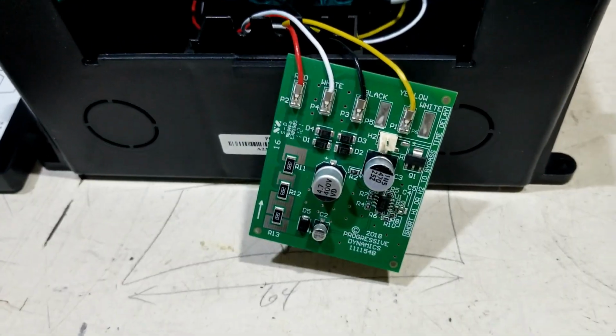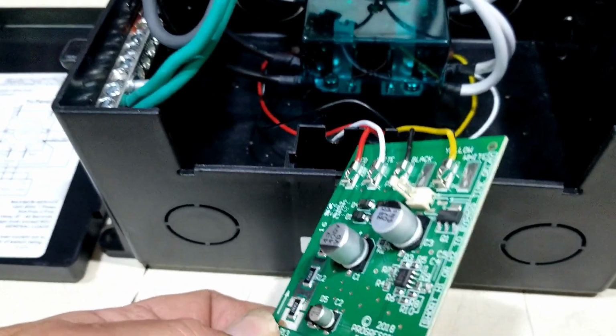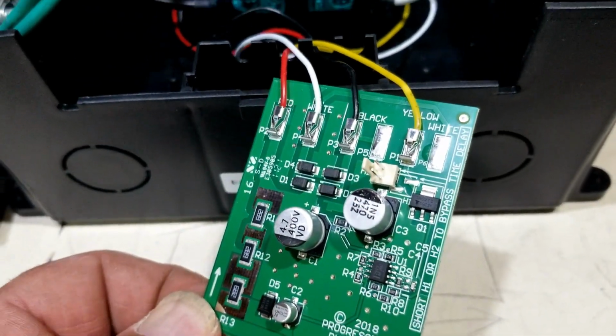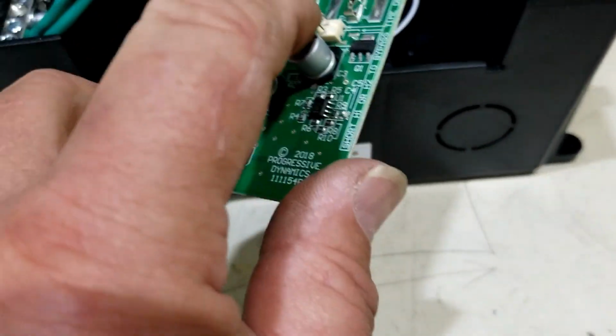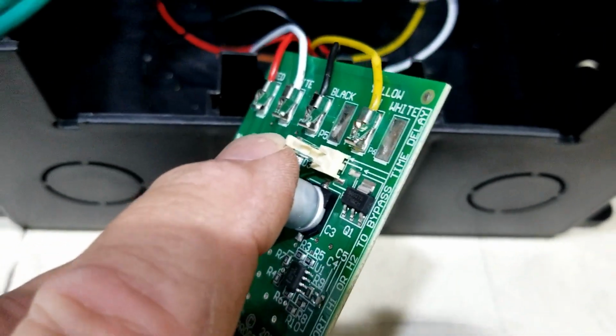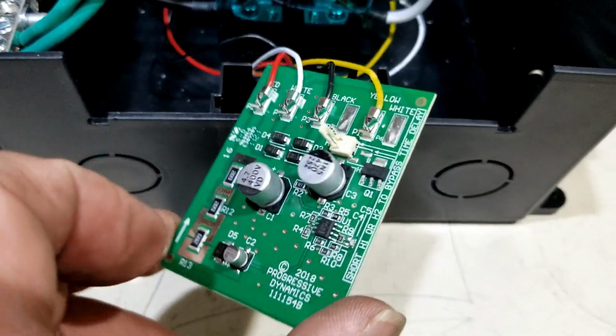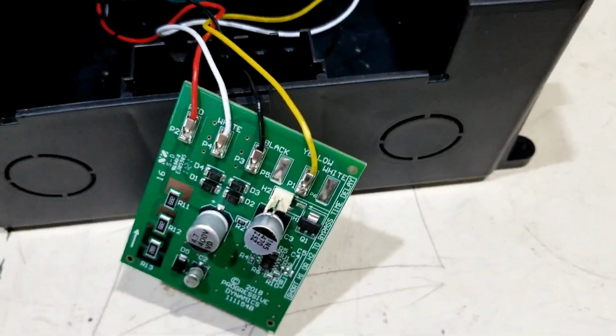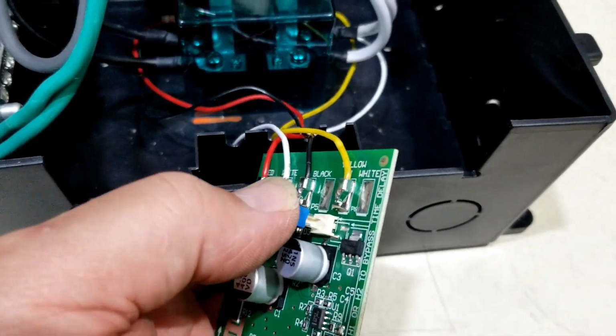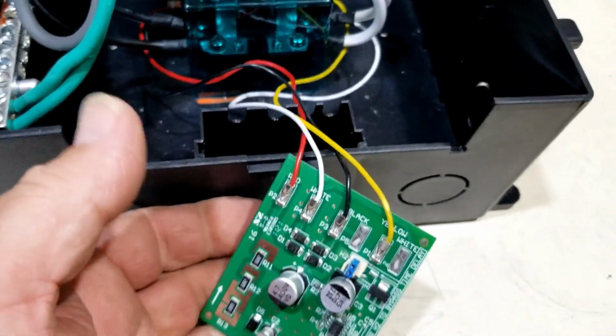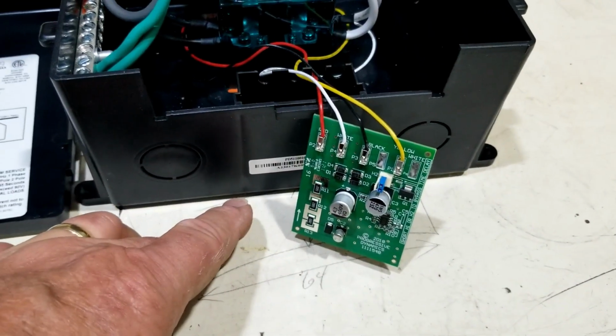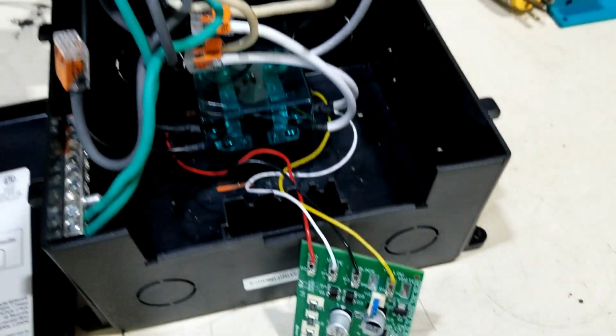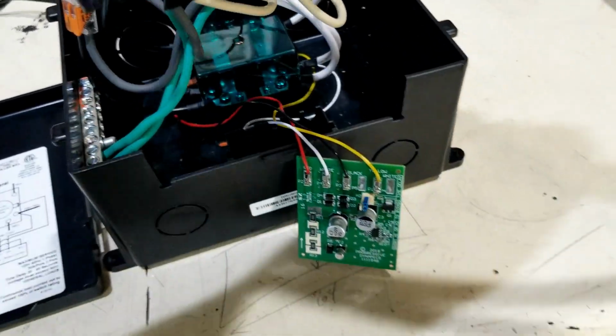This automatic transfer switch comes with a time delay board. There's a set of pins right there that the instruction manual talks about for the time delay circuit. If I put a jumper on these two pins, what I'm doing is disabling the time delay circuit on this board. Let me lay this over here and try not to short anything out.